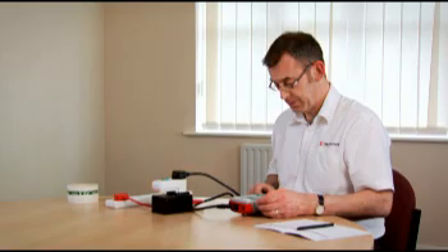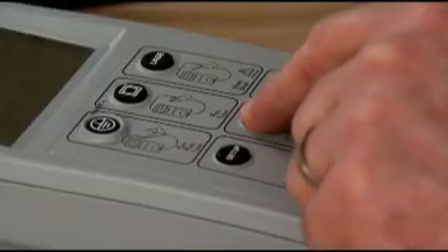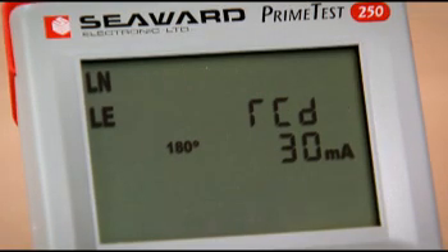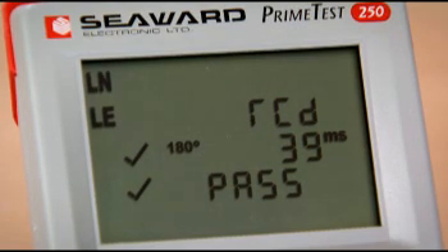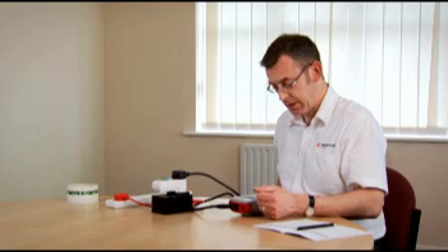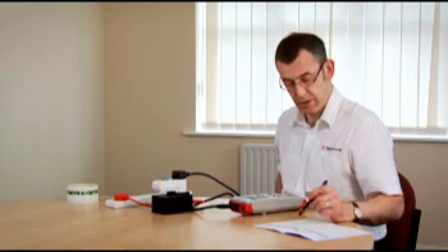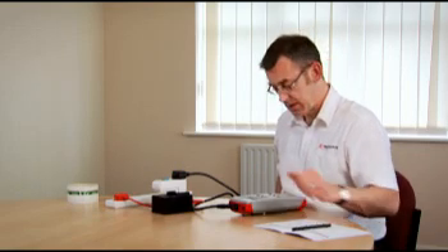We then reset the RCD so it's ready to be tested, and we press the RCD test button here and the RCD trips. We can make a note then of the operating time in our PAT testing logbook and label up the RCD as tested.